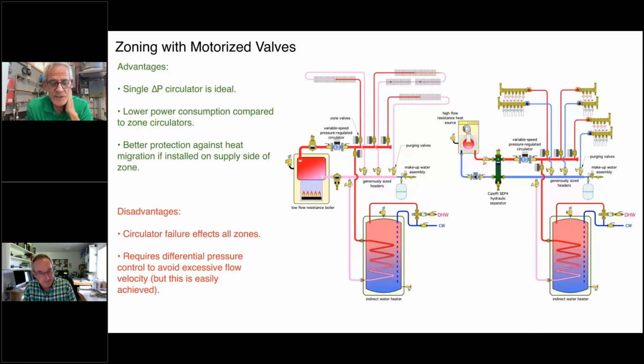So answer me this question, Siggy. It comes up quite a bit. People say, well, if you put the zone valve on the return side of the piping, it has less pressure to close off against. Is that not really true, because as it's closing, as it finally hits its closed position, it's going to have about the same differential pressure.